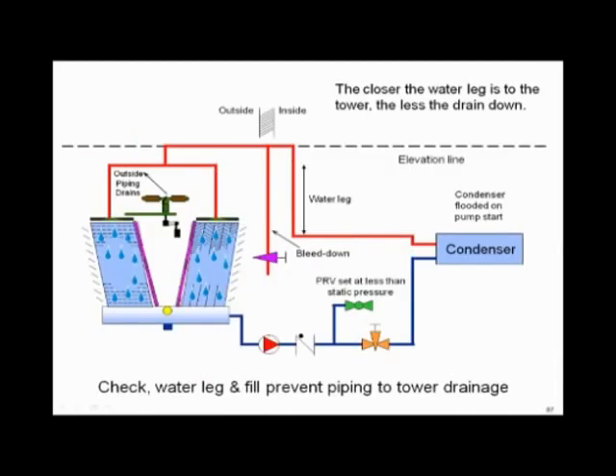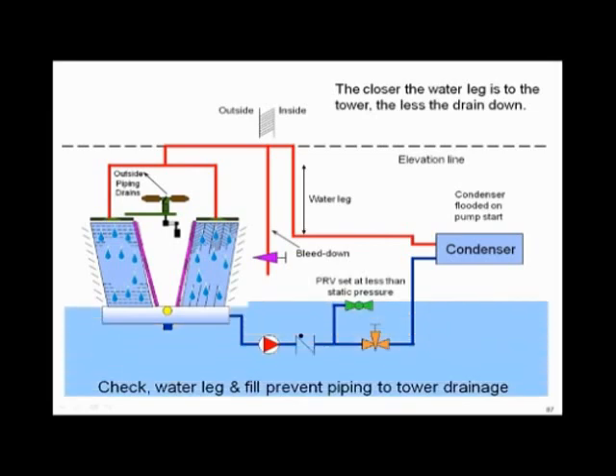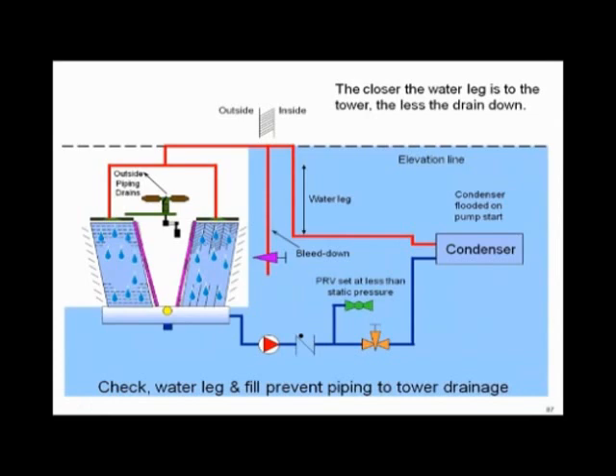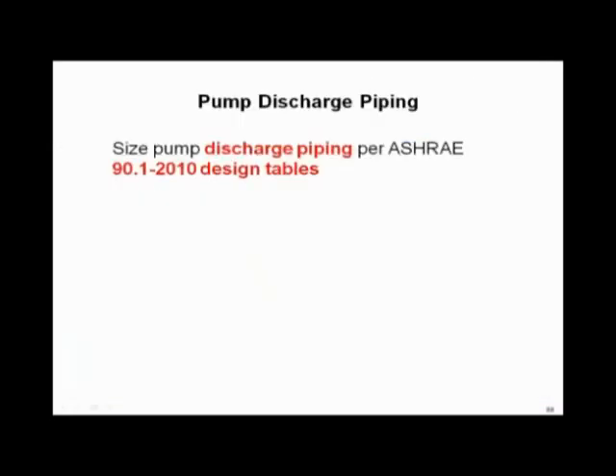A little bit on the discharge side. This is another little pet peeve of mine. It's called a water leg. We've got a triple duty valve on the pump here. And I turn that pump off. Where's the water going to go? I hope everybody sees where the water went. That water leg is trapping the water. So all the discharge piping, all the condenser water piping is full of water with the pump off. So how much water went into the tower? The water went into the tower was in the hot decks of the tower, the fill of the tower, a little bit of overhead piping, but it was not enough to flood the tower. Everybody's happy because of the water leg. You turn the pump back on, you've got plenty of water to get everything going again, there's no problem.